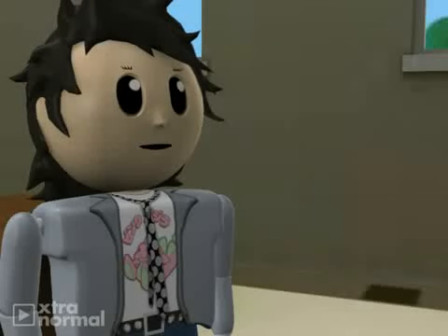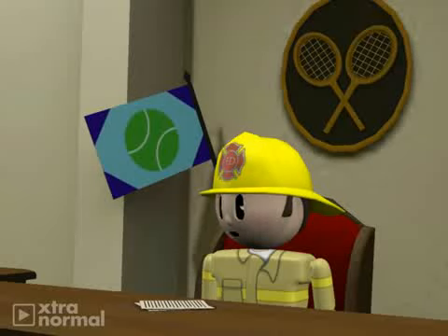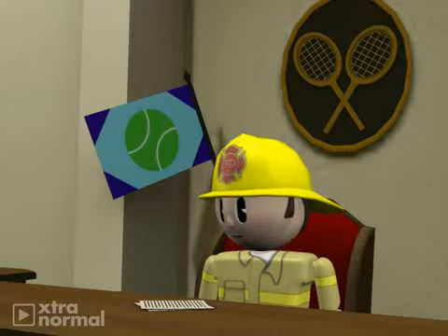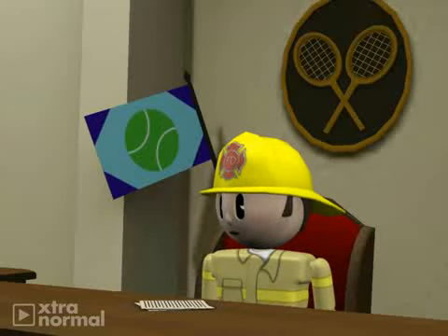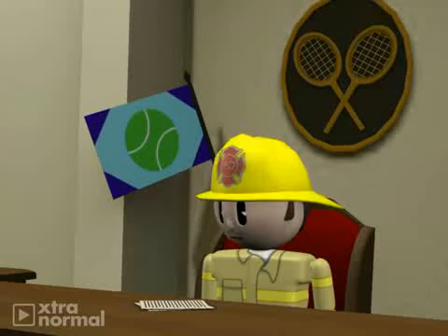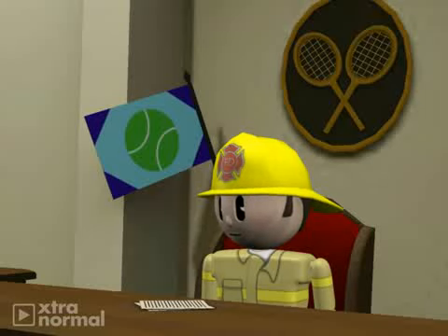What are the differences between low and high pressure water mist systems? High pressure and low pressure systems are tested and approved to the same standards, and systems being approved in accordance with the test standards do also in general have comparable firefighting capability within the type of occupancies which the approval standards cover. The difference between high and low pressure water mist systems is primarily to be found in the nozzle designs, where different means of atomizing water require different water pressures.